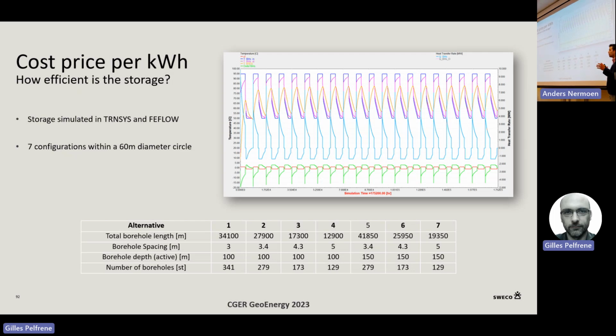If you have more boreholes, the total storage capacity isn't much bigger, but the effect you can deliver is bigger. With more heat exchangers, you can theoretically supply more energy at the beginning of the winter, but then you run the risk of running out of energy by the end of the winter. So we also have to find a balance, since the storage is not infinite — you have a certain volume and can store a certain amount of heat energy.